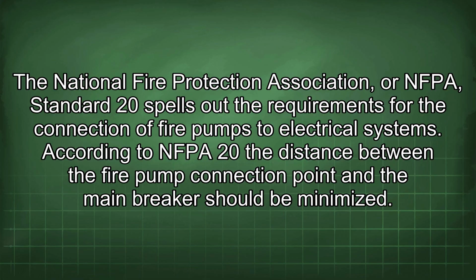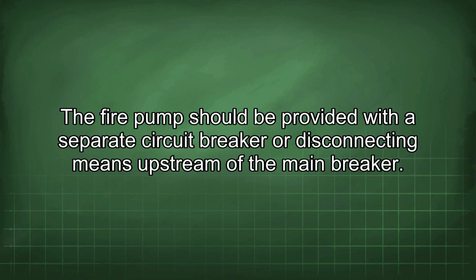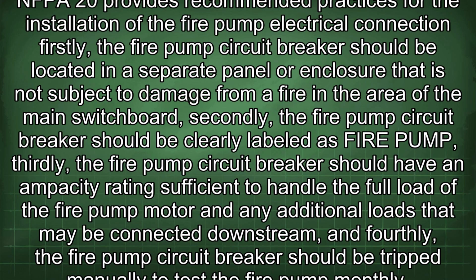electrical systems. According to NFPA 20, the distance between the fire pump connection point and the main breaker should be minimized. The fire pump should be provided with a separate circuit breaker or disconnecting means upstream of the main breaker. NFPA 20 provides recommended practices for the installation of the fire pump electrical connection.